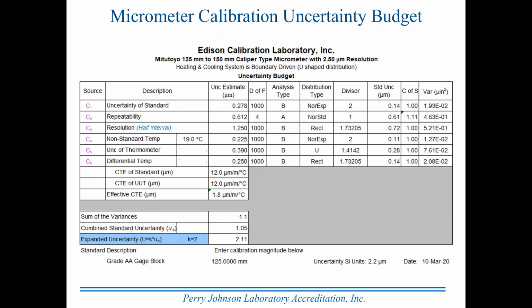Now, a gauge block will always have what's called an absolute uncertainty, because it's the uncertainty of the exact length of the gauge block, not that it's adjustable within a range. It is what it is. But instruments that can measure over a range of sizes, typically the uncertainty is expressed as a relative uncertainty statement, and that way a user can calculate the uncertainty of a measurement anywhere within that range. And that's another topic that is included in the comprehensive uncertainty class. It's a topic on which I think there's some information on Perry Johnson's website that you can download relative to that. We're going to go from this point into the question and answer session.